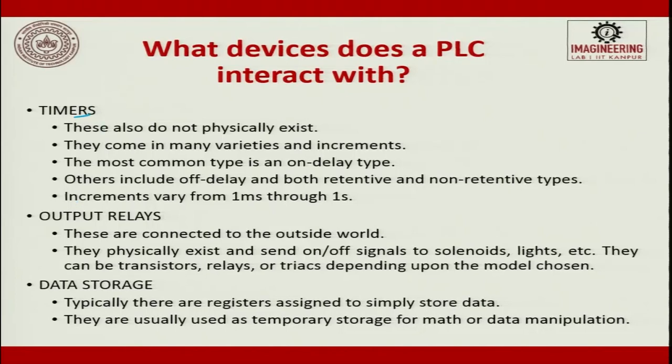Then we have timer. These timers also don't exist in physical form like a clock. It is inbuilt inside the PLC. So here it counts internally. There may be many varieties and increments. The most common type is the on-delay type. The others include off-delay and both retentive and non-retentive types. The increments vary from 1 millisecond to 1 second.